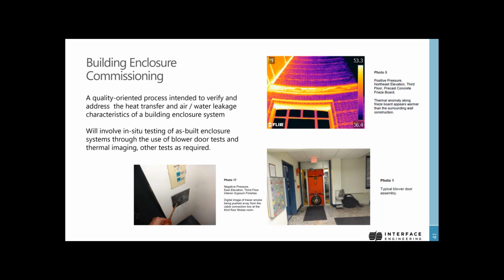We can take a picture of the facade at night. In this case, we were doing this at night in Portland when it was about 20 degrees outside, looking at how heat escapes from the building. What you can see here is that the bright orange sections of the facade are a frieze board that was not properly thermally bridged from the rest of the building. The architect had detailed it to be thermally isolated, but it wasn't built with that detailing properly, so we're seeing a lot of heat loss. If the surface of that frieze board is 53 degrees when it's 20 degrees outside, that means we're losing a lot of heat through that portion of the envelope. The contractor had to go and remedy that condition.